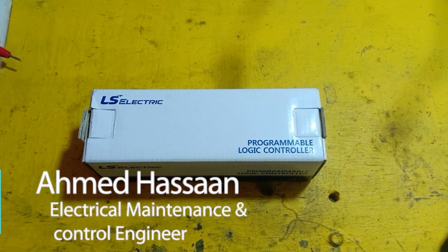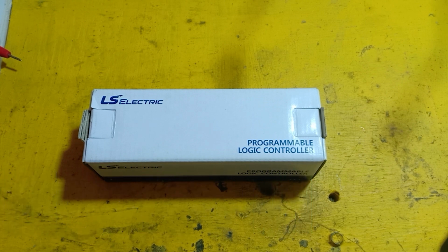Here I have a malfunction of a Smart I/O that is connected to an LS PLC, the kind of distributed I/O. This fault causes the loads, which are fans and blowers driven by 7.5 kilowatt motors, to delay running because of that error. So I have to change that distributed output module.